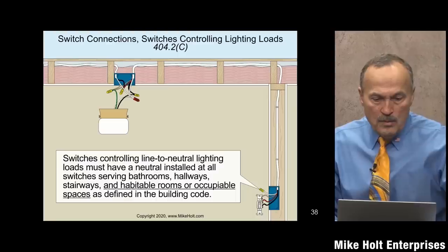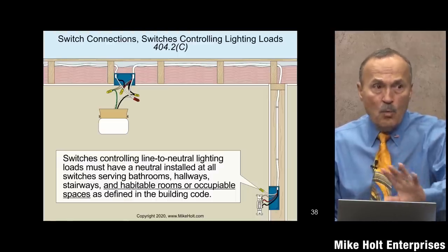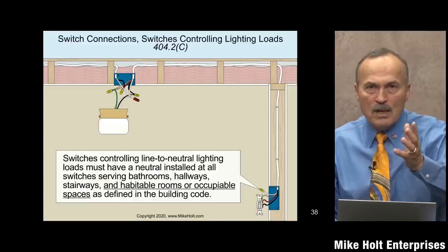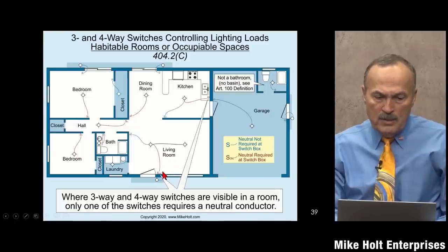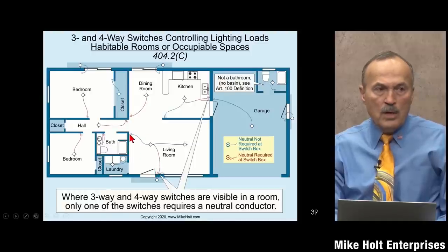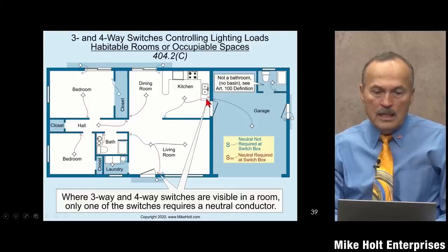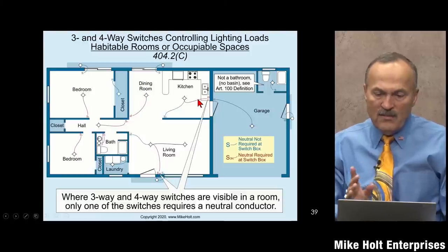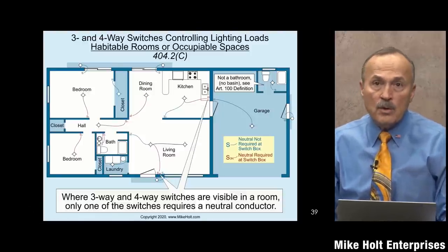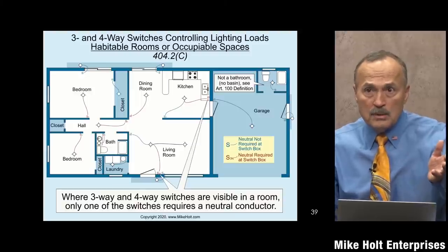The basic rule: you need a neutral, but the code tells you where. For three- or four-way switching where all switches are visible in the same room, you only need a neutral at one of those switches. For example, in a kitchen with two three-way switches, only one switch needs a neutral — the graphic highlights in red exactly which switch requires it.